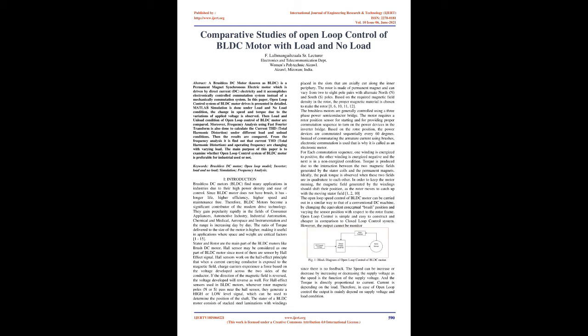Stator and rotor are the main parts of the BLDC motor, like brush DC motors. Hall sensors may be considered as one part of BLDC motors since most of them are sensed by Hall effect signals. Hall sensors work on the Hall effect principle: when a current-carrying conductor is exposed to a magnetic field, charge carriers experience a force based on the voltage developed across the two sides of the conductor. If the direction of the magnetic field is reversed, the voltage developed will reverse as well. For Hall effect sensors used in BLDC motors, whenever rotor magnetic poles (N or S) pass near the Hall sensor, they generate a high or low level signal which can be used to determine the position of the shaft.